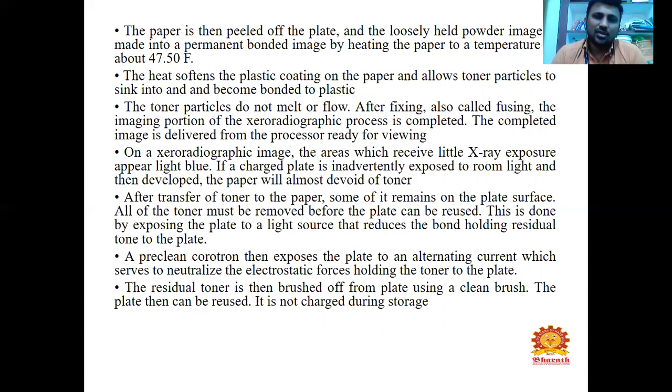The imaging portion of the xeroradiography process is completed. The completed image is delivered from the processor ready for reviewing. On a xeroradiographic image, the areas which receive little X-ray exposure appear light blue. If a charged plate is inadvertently exposed to room light and then developed, the paper will be almost void of toner. After transfer of toner to the paper, some of it remains on the plate surface. All of the toner must be removed before the plate can be reused.